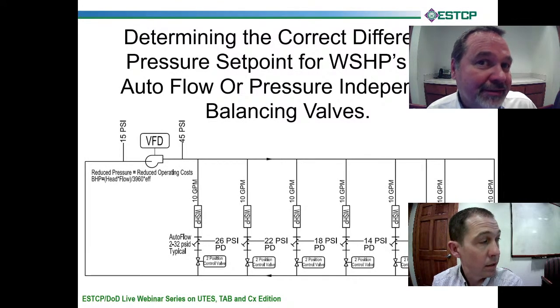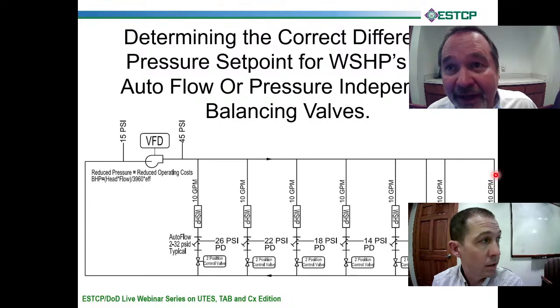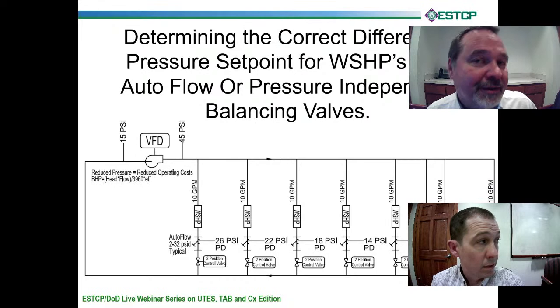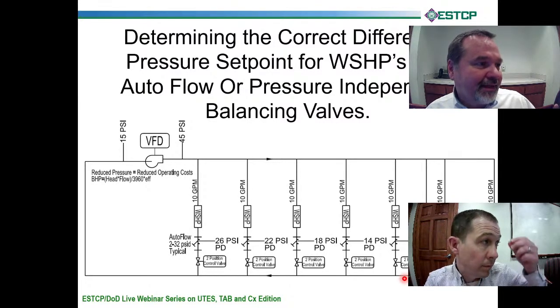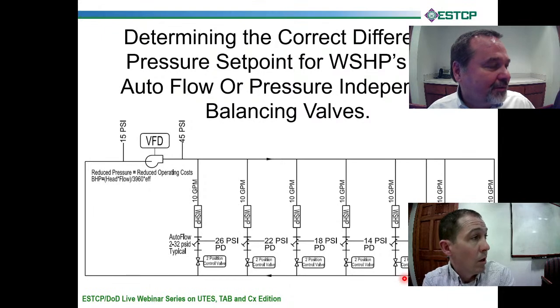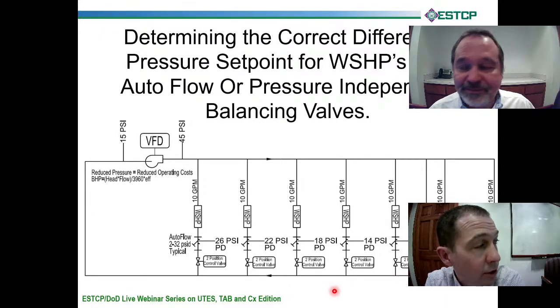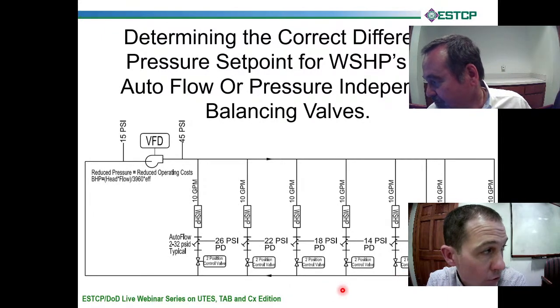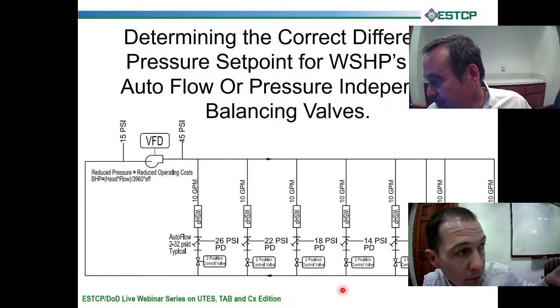So we're talking about a differential pressure of maybe 10 PSI at that pressure transducer, then there's PD through this pipe, and there's PD through the water source heat pump, and then we need to have at least 2 pounds difference across there. But we're just trying to get an average reading, so that's why this differential pressure is connected between these two mains right here, trying to make everybody happy down through there. And as Brandon mentioned before, with dynamic set point adjustment, we can keep backing that down as low as possible. On systems that don't have automatic flow control, I mean, this is water source heat pump 2-position control valves.